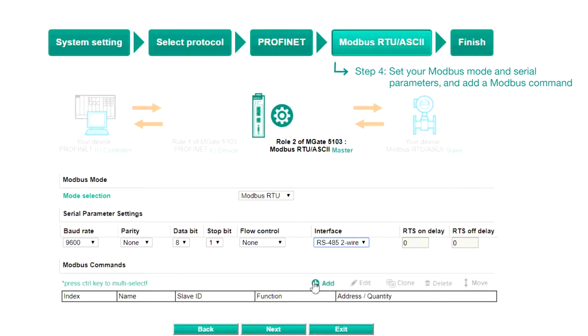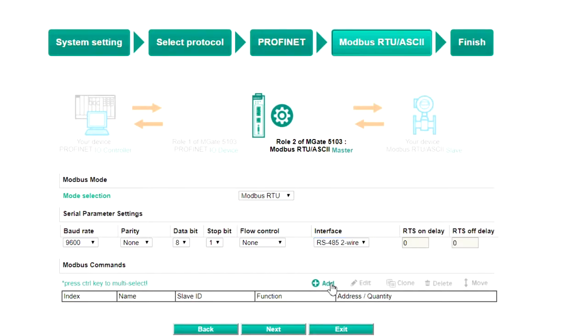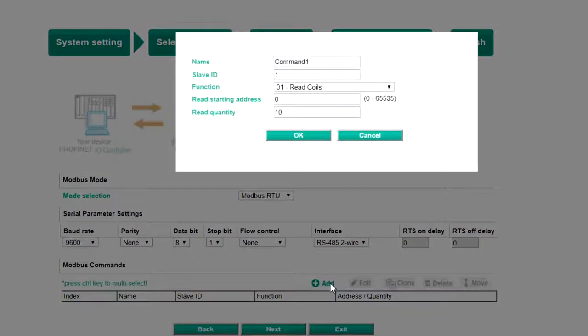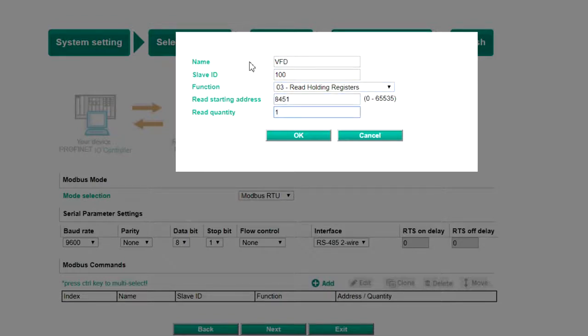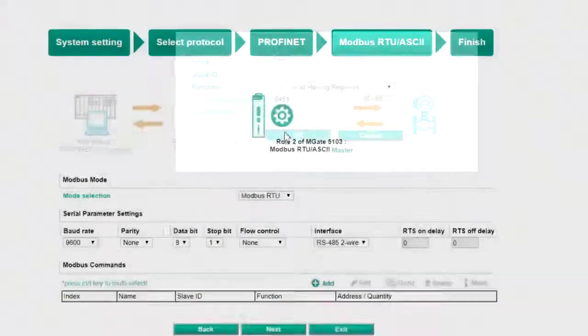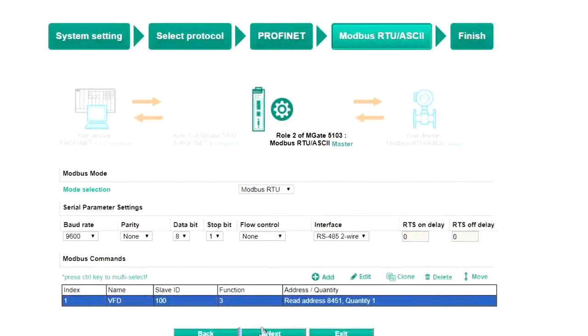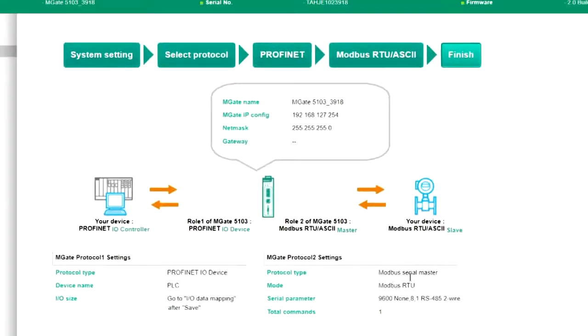To control the speed of the VFD in this demo, we will need to click Add to add a Modbus command. Fill in the details as needed, such as the slave ID, function code, read address, and read quantity. Click OK, then click Next to view the summary page.